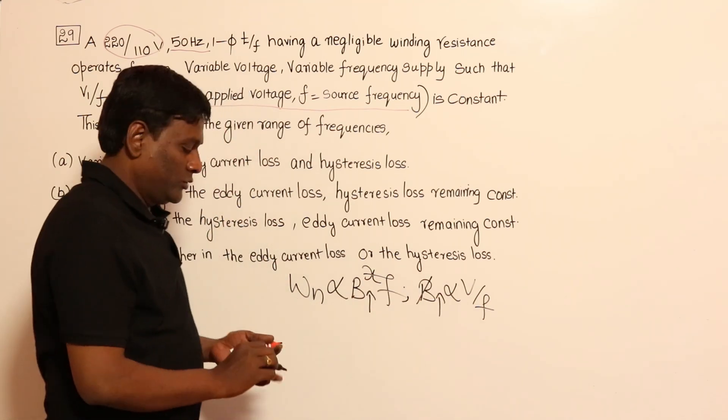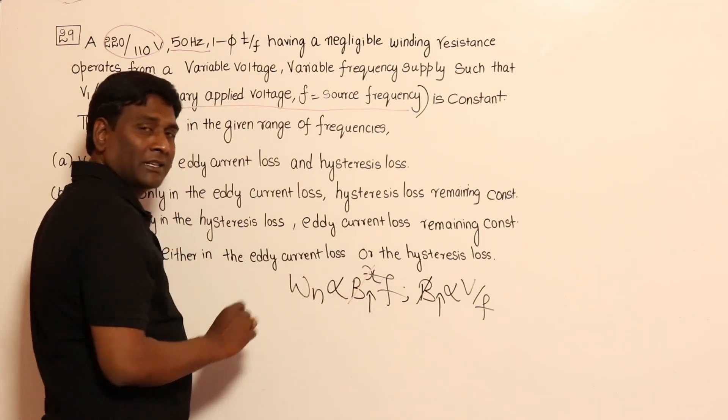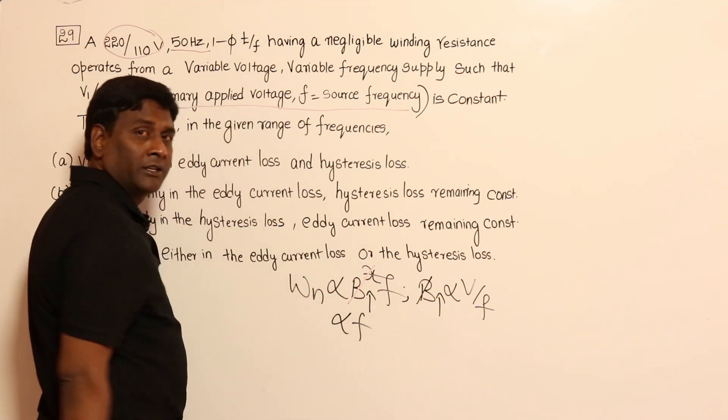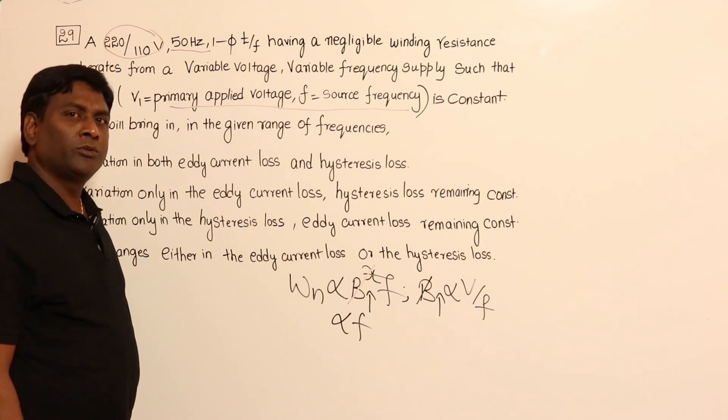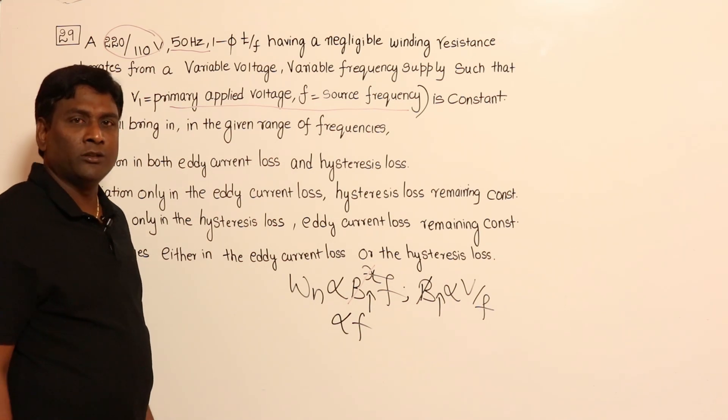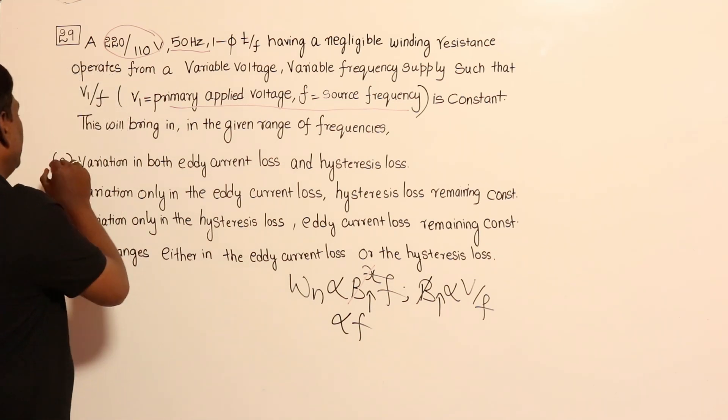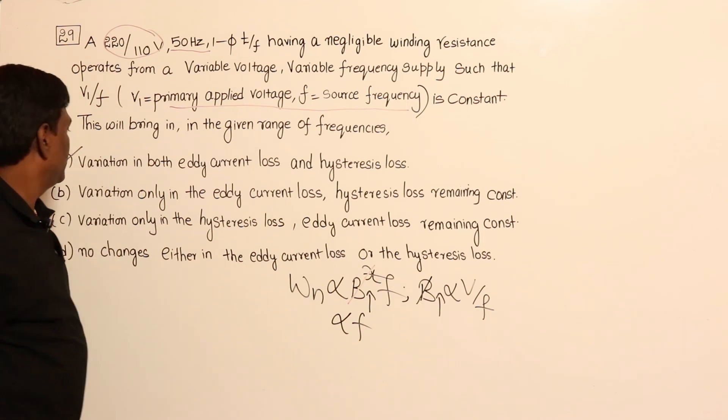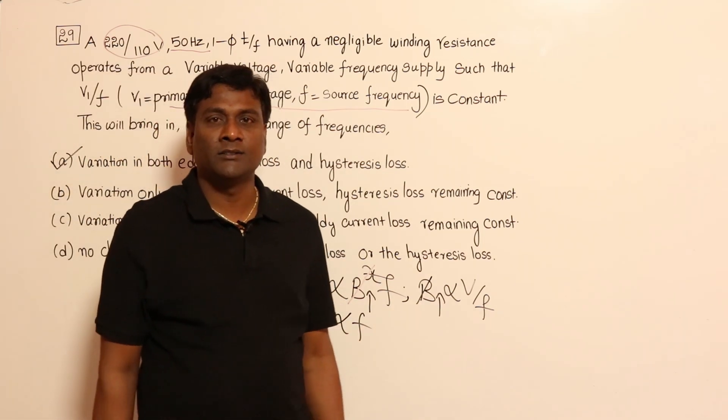If B_max is constant, hysteresis loss is directly proportional to frequency. Frequency is variable here, so automatically hysteresis losses also should vary. So the answer should be: variation will happen in both hysteresis and eddy current losses.